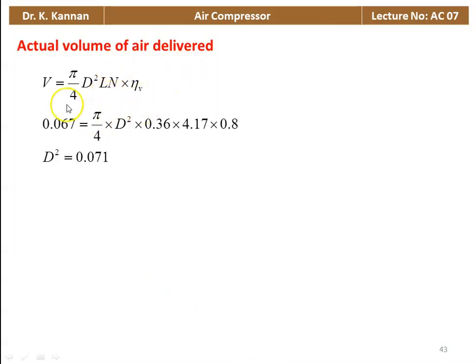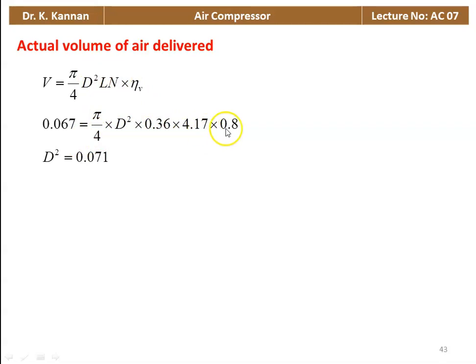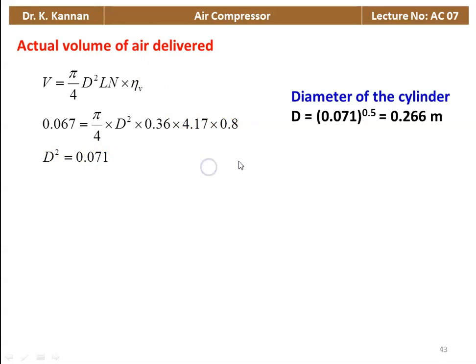Actual volume of air delivered V = (π/4) × D² × L × n × volumetric efficiency. Substituting: 0.067 = (π/4) × D² × 0.36 × 4.17 × 0.8. Solving, D² = 0.071, so diameter D = √0.071 = 0.266 meter.